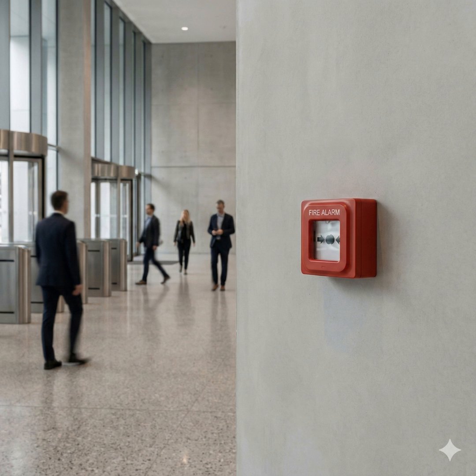Okay, moving from the science of detection to the resilience of the network itself, we're now shifting our focus to how the system maintains its integrity, basically the security view of the fire network. And that divergence between conventional and addressable systems is maybe the most fundamental choice a designer makes. Conventional systems are simple. They group sensors into zones. A signal means a fire somewhere in that zone.